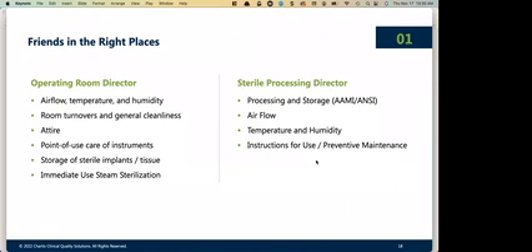And then the last kind of issue we look for is immediate use steam sterilization, which in most places is going away. People are using it less and less. But one of the main things we find is that the less you use it, you have to determine who is actually performing the immediate use steam sterilization. Is it OR staff or is it sterile processing staff? If it's OR staff and they're doing it 4 times a year or 4 times a month, then it's hard for them to keep competencies. And so you have to really watch for competency with immediate use steam sterilization.